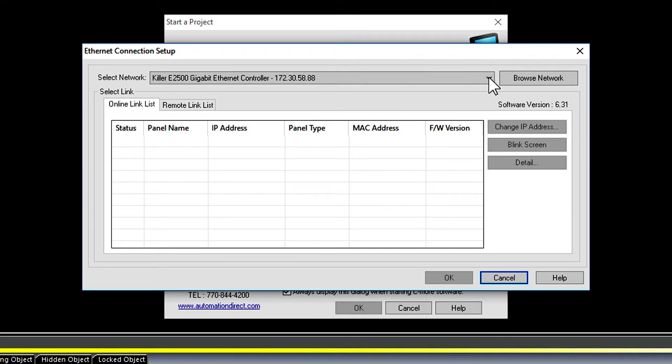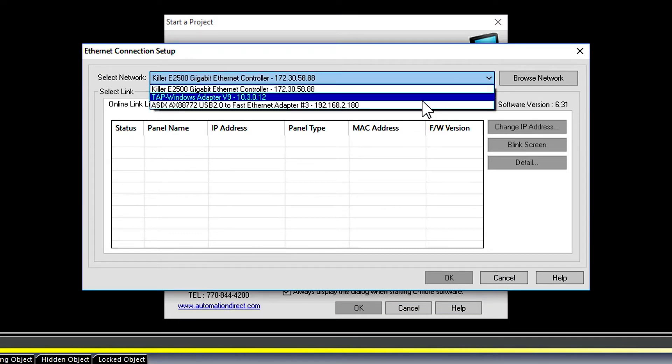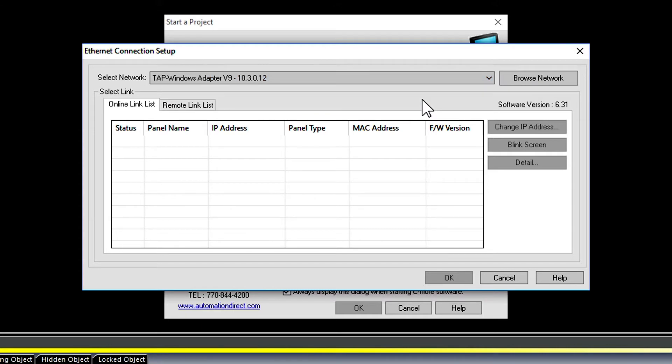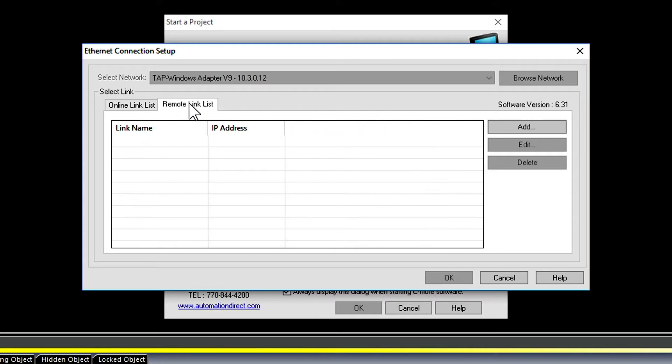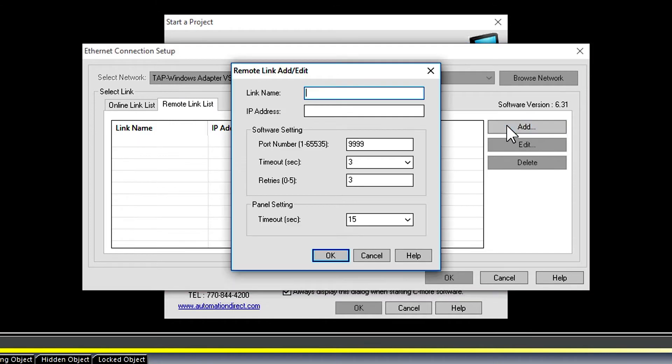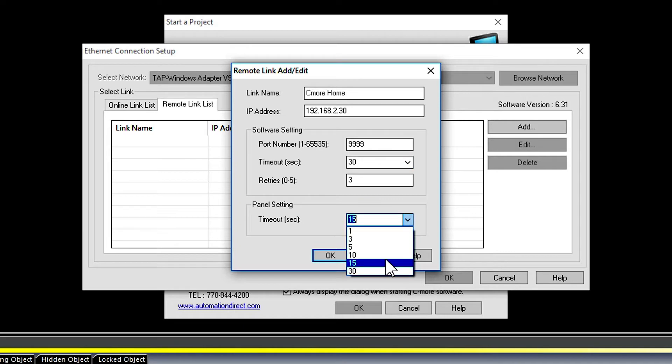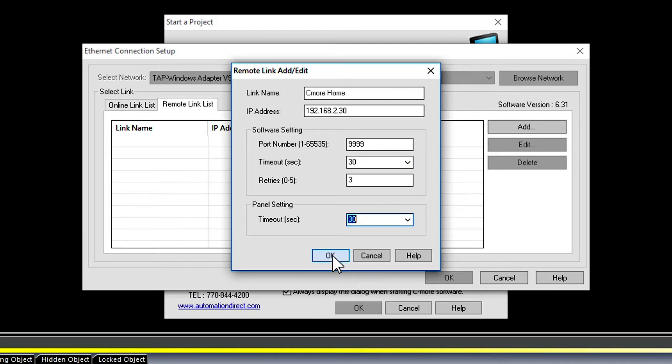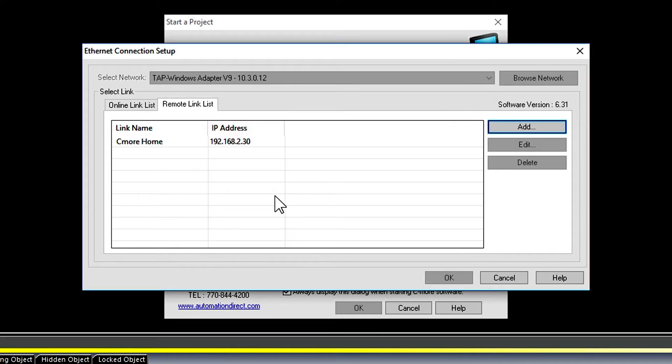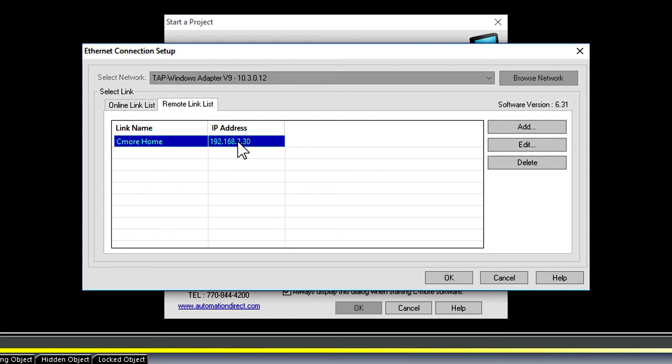Under Network select the Windows Tap Adapter. This is the virtual connection that the IX client uses to connect to the VPN cloud. Now select the remote link list and then Add. Give this connection a name. Enter in the IP address of the C-more panel and then typically on a remote connection like this I will increase the timeouts to the max. Hit OK. Now select the link that we just created and select OK.